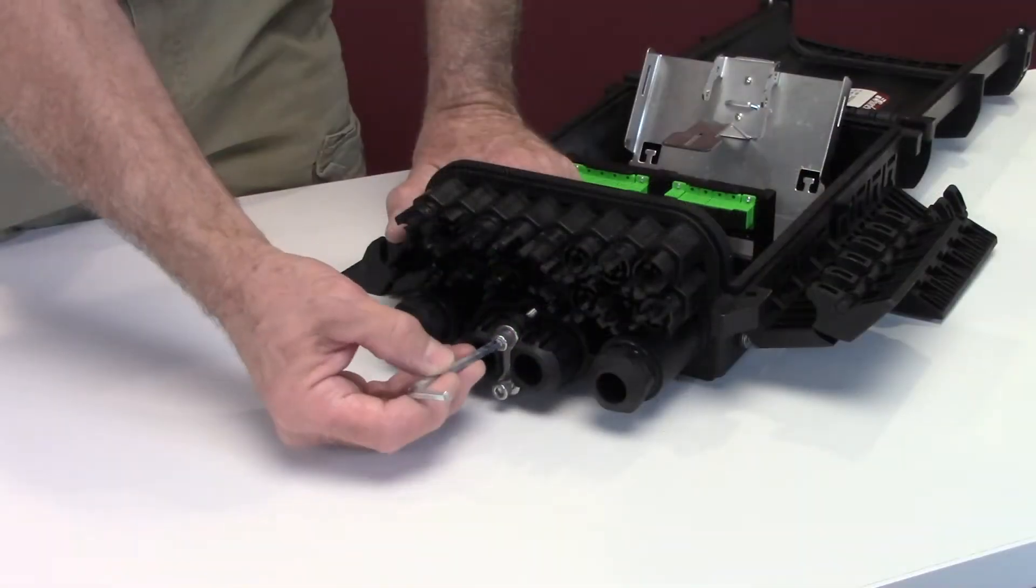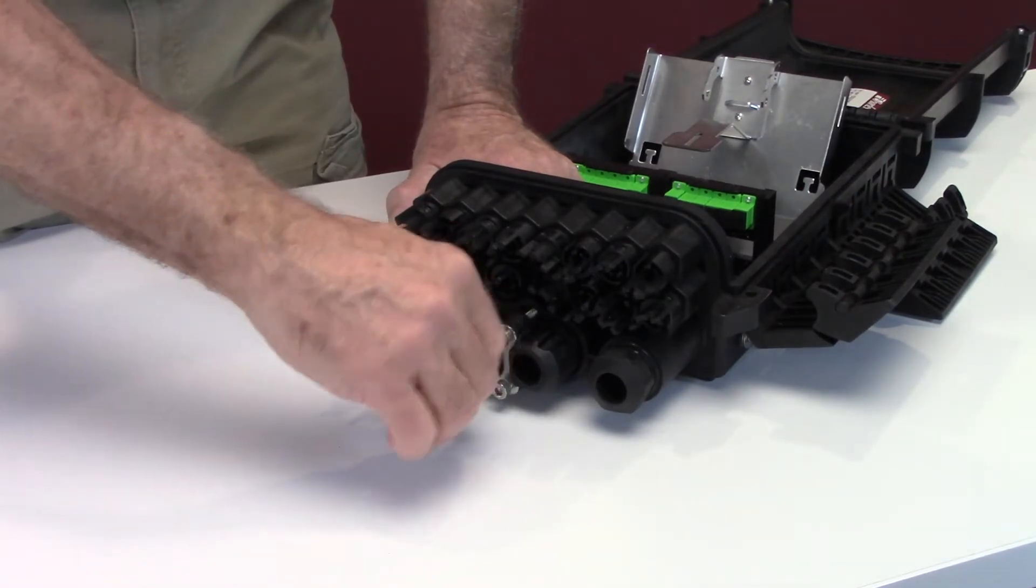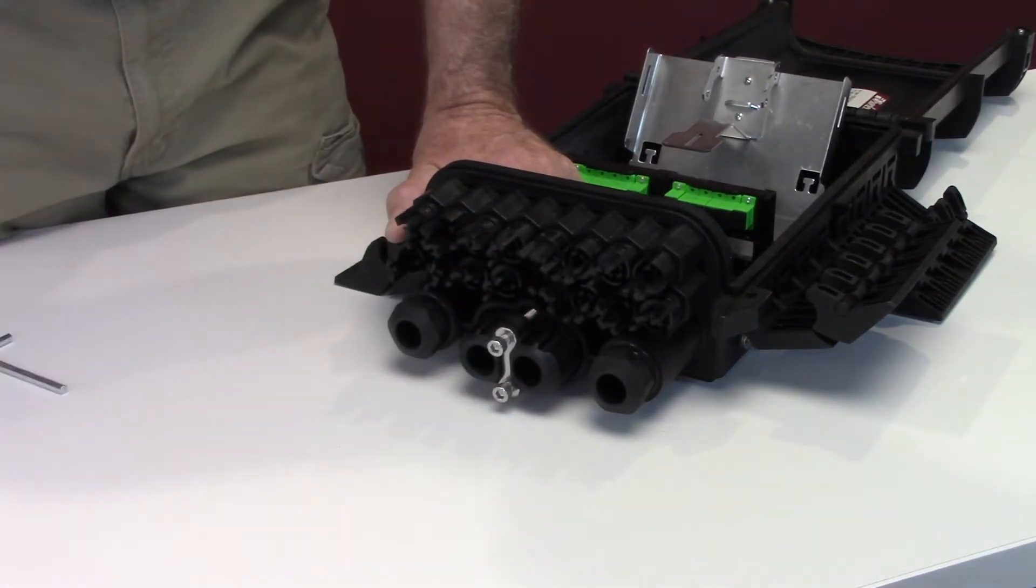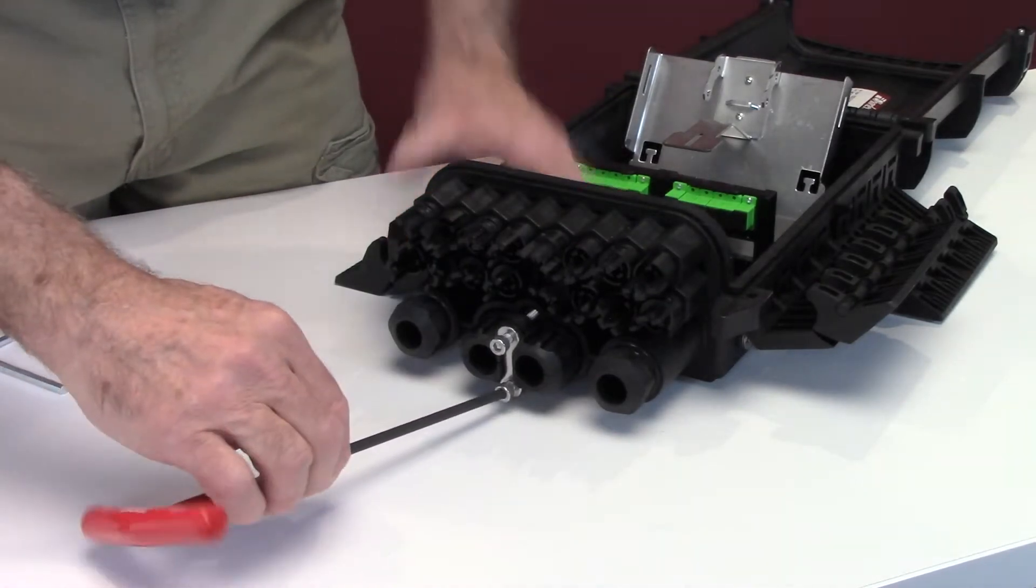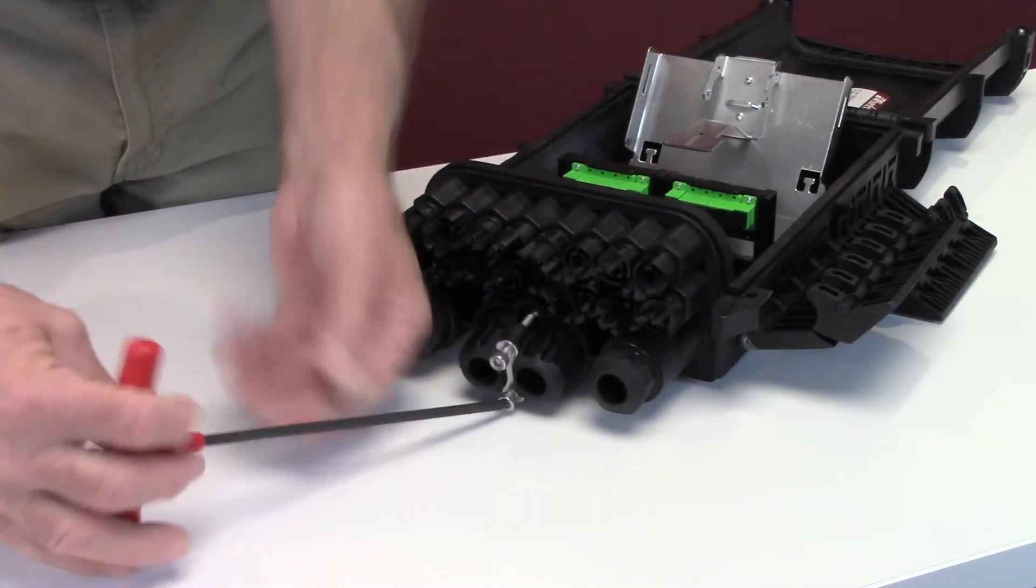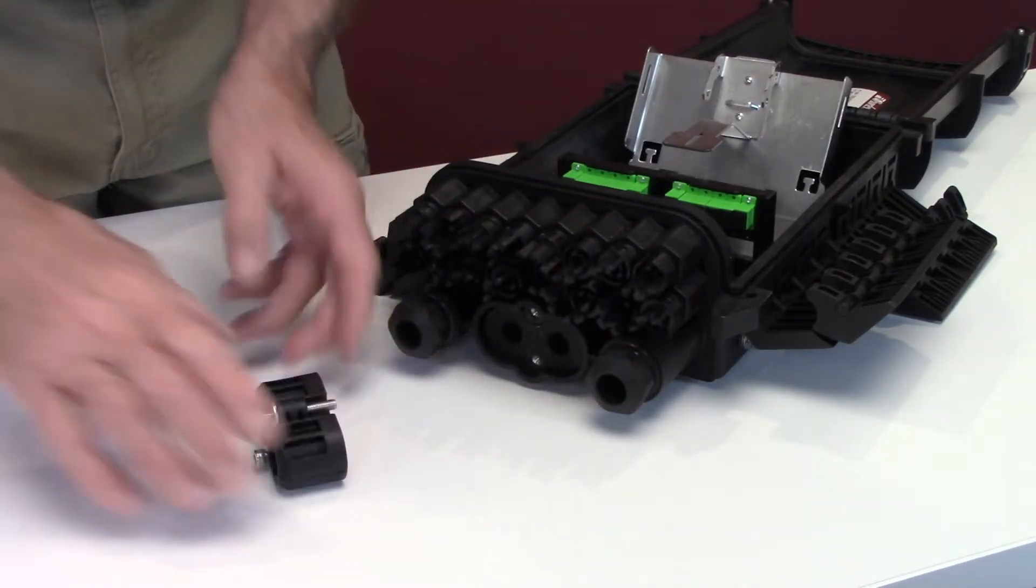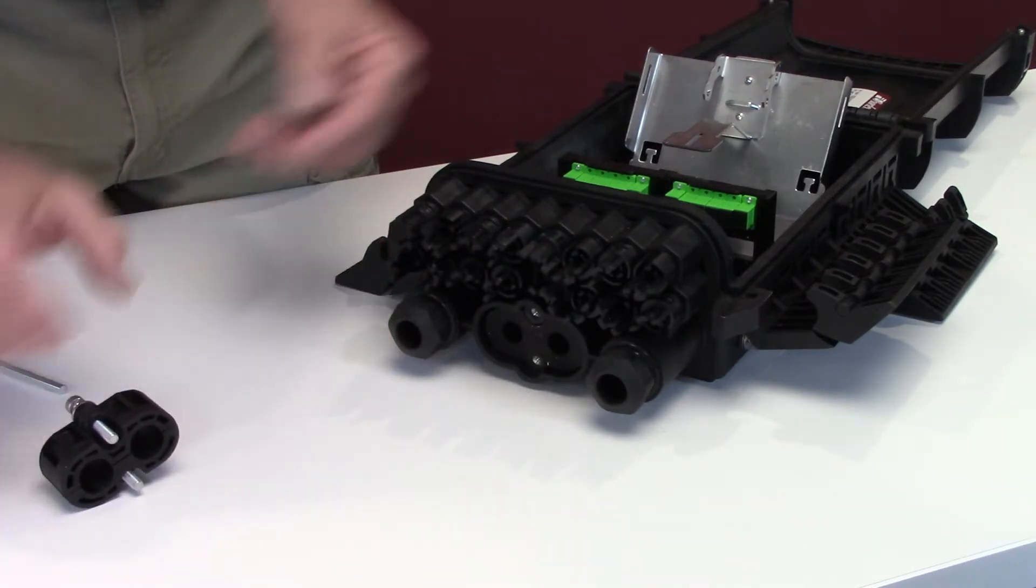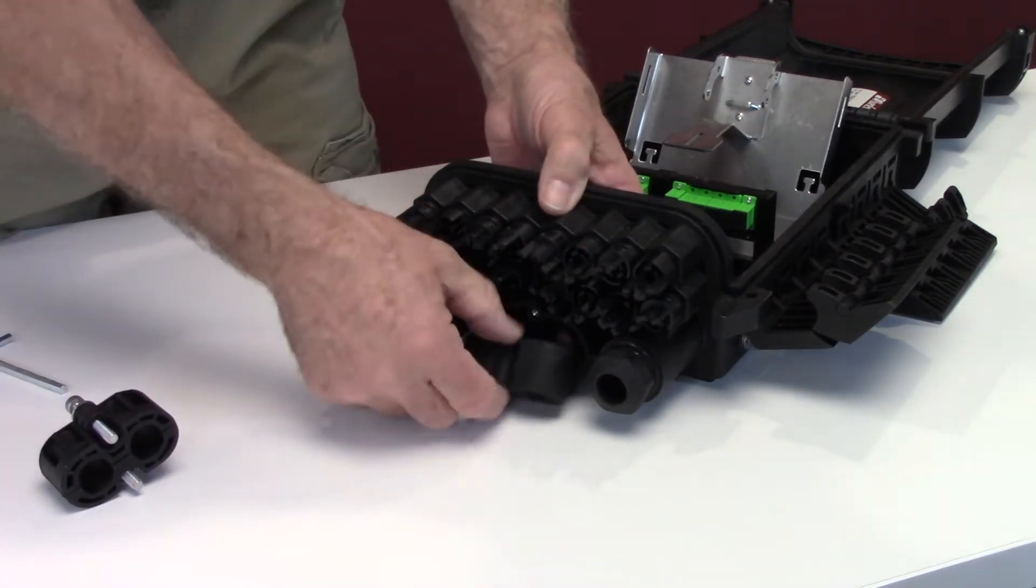Use the supplied five millimeter Allen wrench or a T-handled Allen wrench to loosen the express port sealing components. First the cable clamp, then the sealing grommet, finally the plastic inner grommet. A three sixteenths inch Allen wrench can be substituted for the five millimeter wrench.